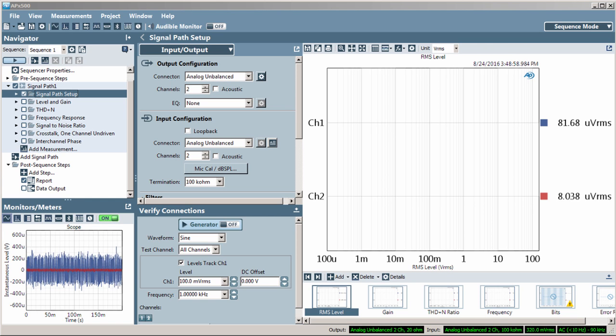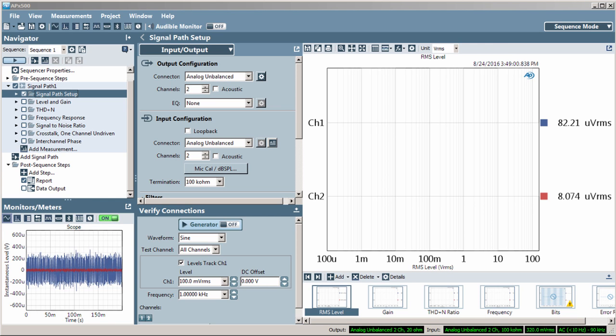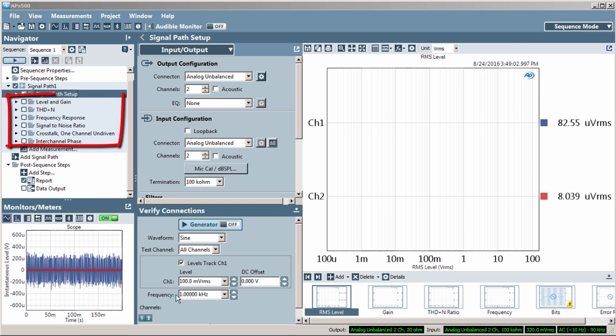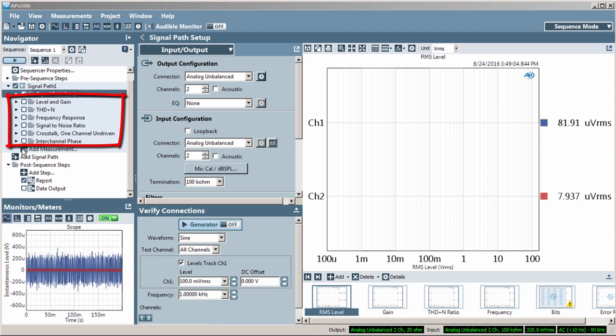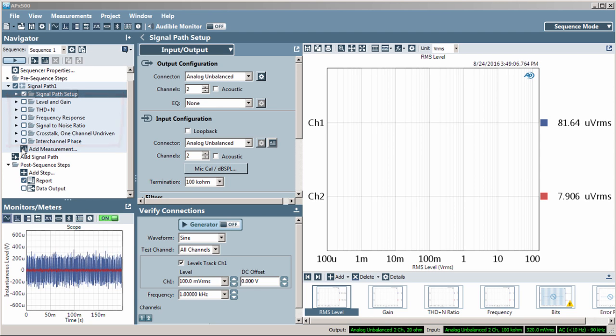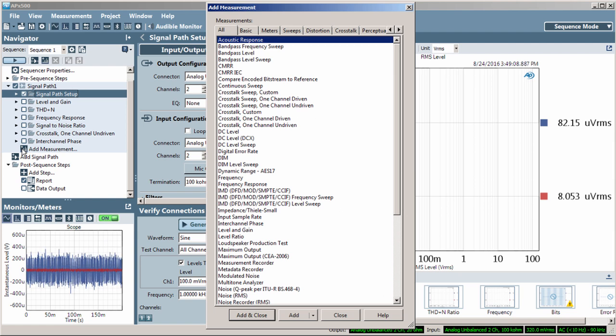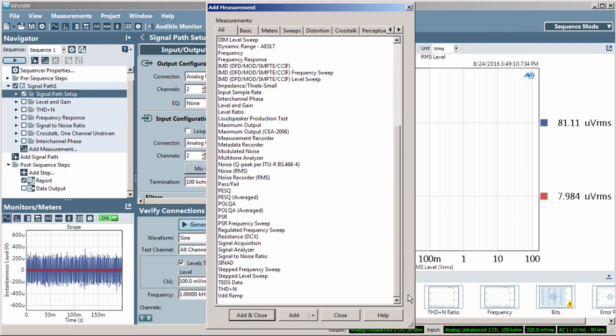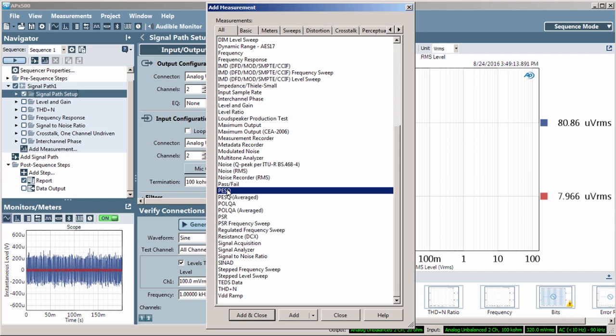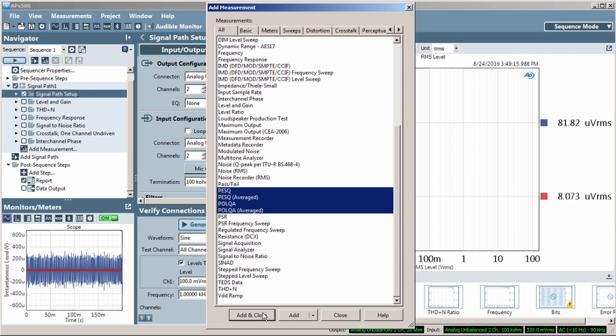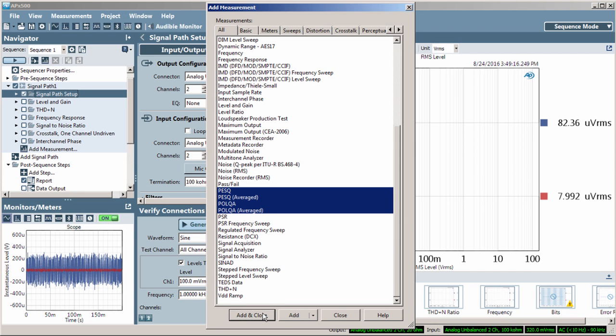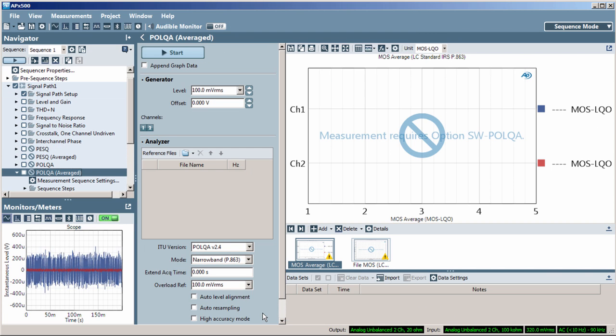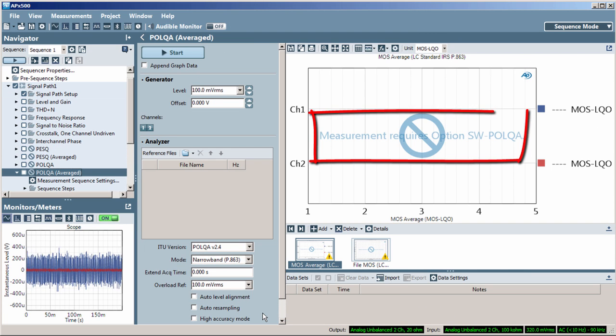APX500 software comes standard with many measurements. The big six are included with the default new project file. Click the Add Measurements icon and you'll see the complete list of available measurements. Some measurements and features are optional and require a purchased license key.